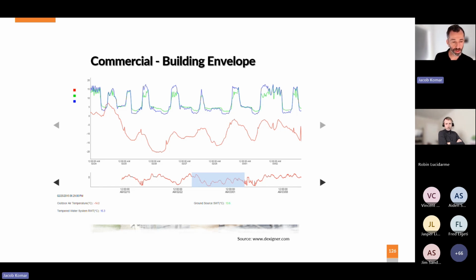The interesting thing is we got some data back from this building in February. They were just partially occupied. This red line shows it was about minus 12 degrees outside, so freezing. The green line is the temperature coming from the ground, and the blue line is the temperature going back from the ground into the ground. So basically, anytime the blue line is above the green line, it means we're rejecting heat to the ground. The blue is what we're sending to the ground, the green is what's coming back.